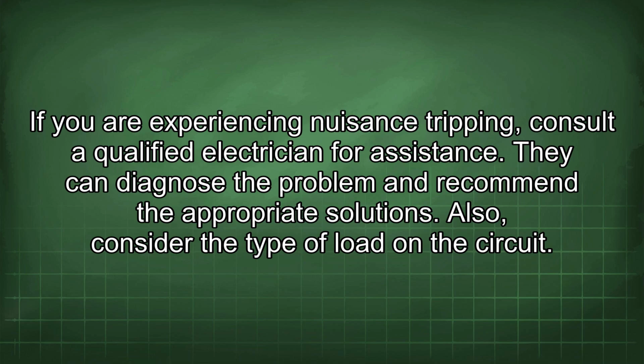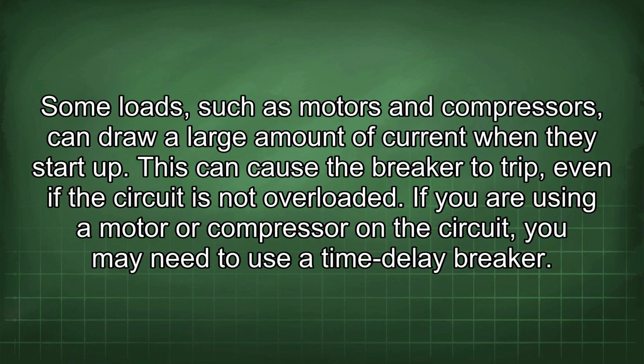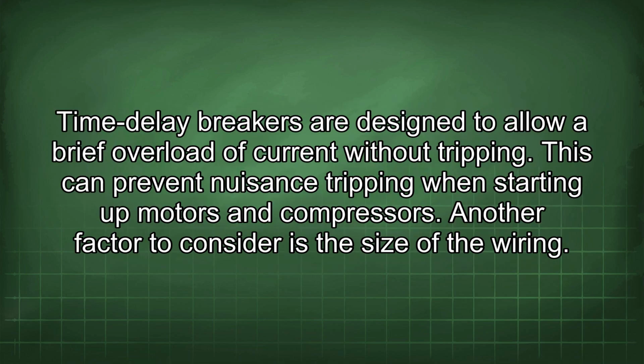Also, consider the type of load in the circuit. Some loads, such as motors and compressors, can draw a large amount of current when they start up. This can cause the breaker to trip, even if the circuit is not overloaded. If you are using a motor or compressor on the circuit, you may need to use a time delay breaker. Time delay breakers are designed to allow a brief overload of current without tripping. This can prevent nuisance tripping when starting up motors and compressors.